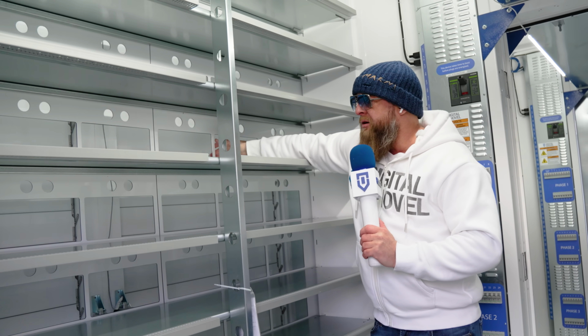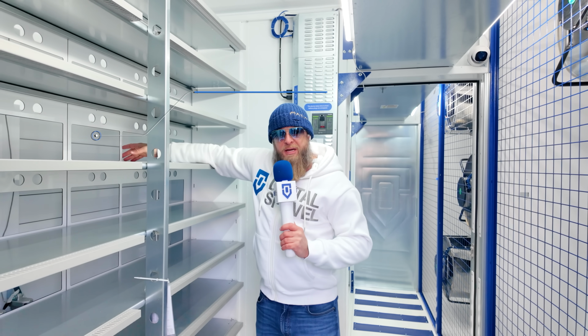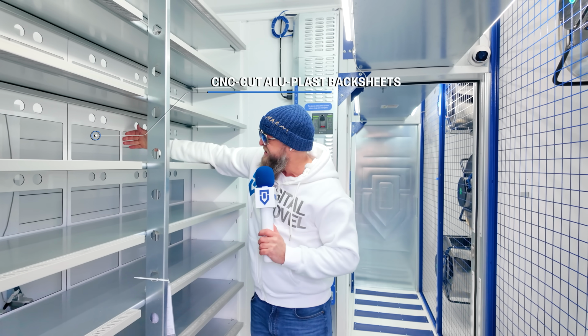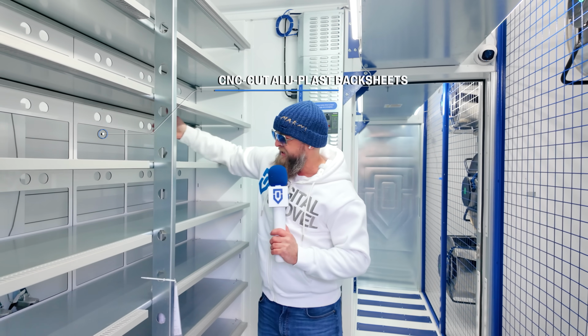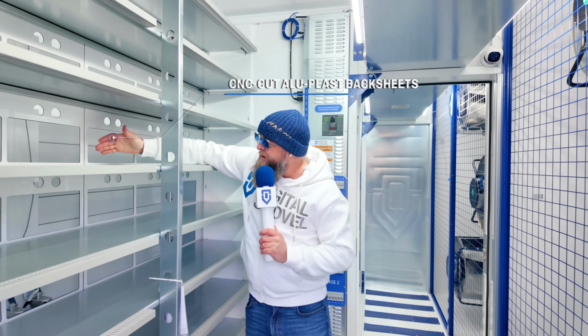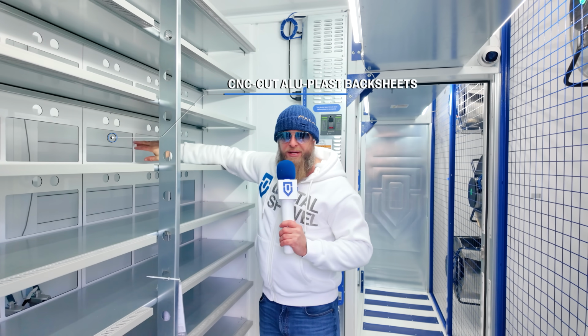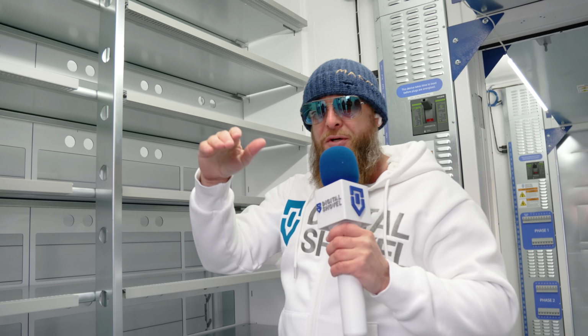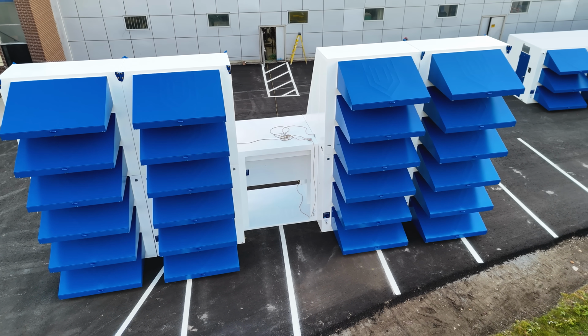We've got our new hot aisle containment sheets, which these new panels are made out of an alu panel material, which actually has a PVC filling on the inside and then aluminum on the outside. We cut it with a CNC router with a beveled edge that actually creates a small circumference. So what's actually rubbing on the miner is now just a plastic edge rather than the CNC cut metal containment back sheets that we had before. Let's go over and check out the Gen 3 double stack so I can show you the difference between the two.